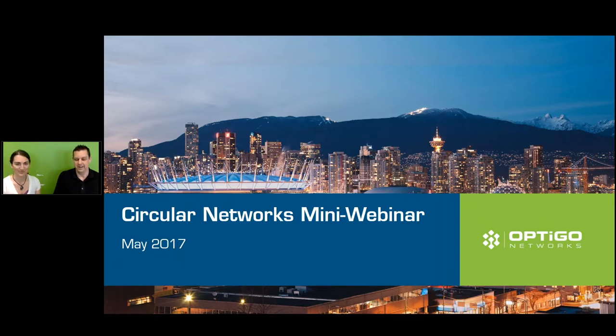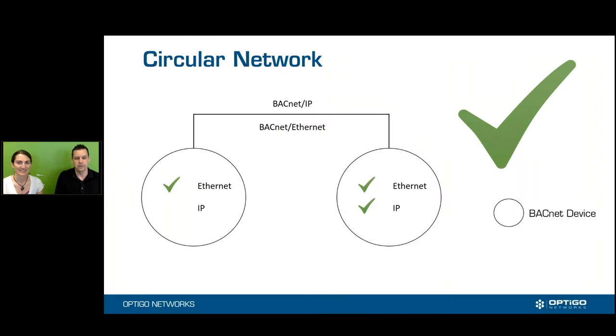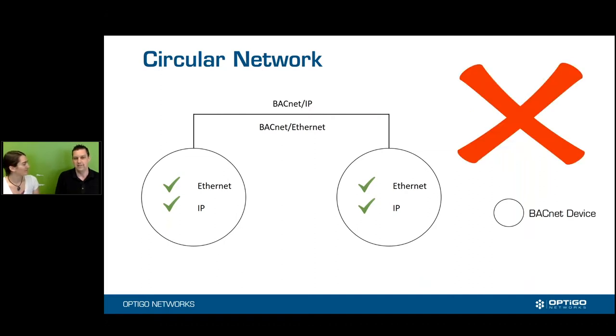A circular network — they're a nasty little thing when they come up. I'll show you quickly on the screen what it looks like. This obviously is not a circular network. This is something where one controller is doing the routing between IP and Ethernet, and the other one is either IP or Ethernet. Where you get into trouble is when you have both of those checked on two controllers, meaning there's a path going from each controller on Ethernet and the same path on IP. That's a bad thing.